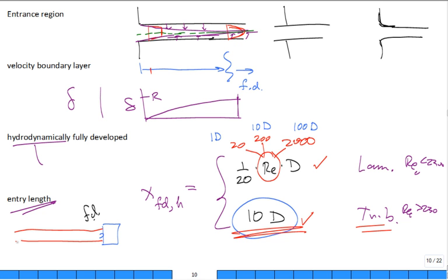And they traced it to the flow meter not having the correct inlet conditions, and had to figure out how to recalibrate it, make adjustments to compensate the injured party, the person who had been overpaying, and rectify the situation. It happens a lot. Okay?